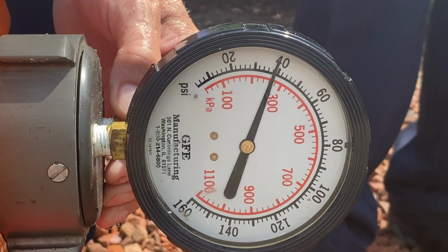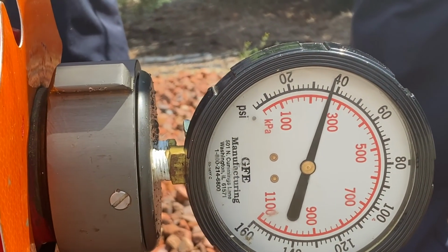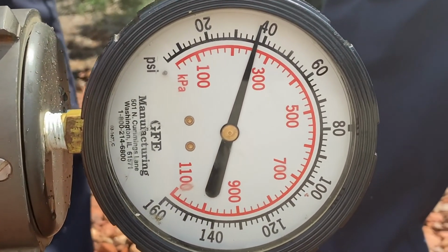The second procedure during a hydrant flow test is to measure the static, non-flowing water pressure. This is important because it lets firefighters know how to operate fire apparatus and hose lines during structure fires. Sufficient water pressure is critical to our operation. Without it, we would cavitate pumps, collapse water lines, have to rob the operating fire sprinkler system, and even pull water from water heaters, allowing fire to grow out of control.